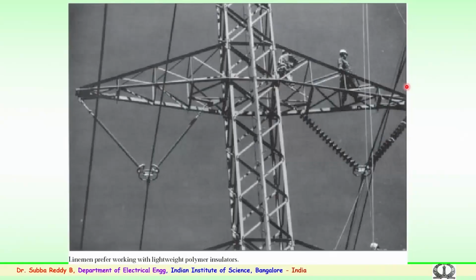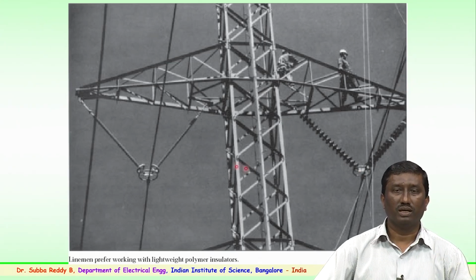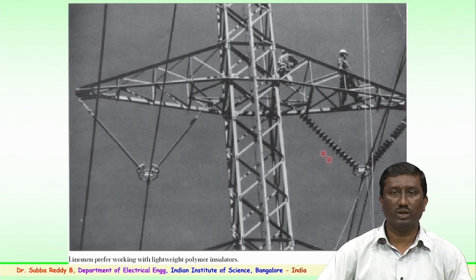So, welcome back. We were looking into the transmission tower, where the linemen prefer working with lightweight polymer insulators instead of the ceramic or glass type of insulators, which weigh more. Just for comparison purposes, you can see the two insulator strings, a polymer insulator string and a ceramic or porcelain insulator string. Typically for a 400 kV system, the number of insulators will be somewhere around 23 to 25 disc insulators each side.